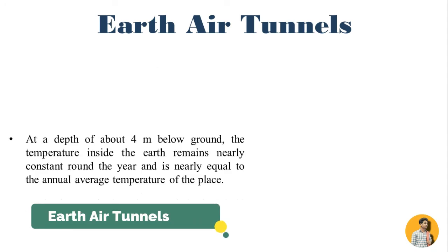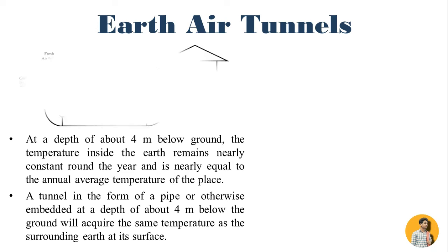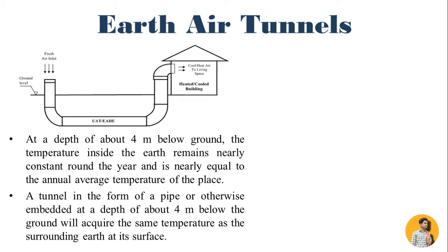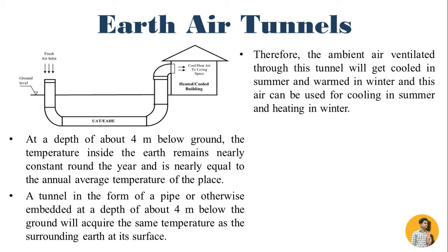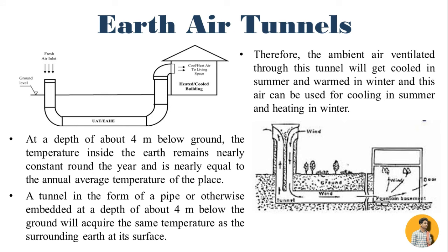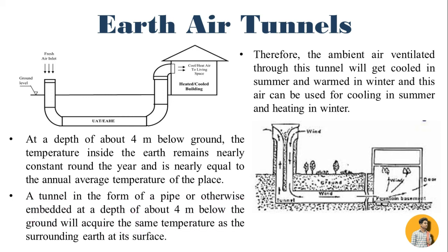Earth air tunnels: at a depth of about 4 meters below ground, the temperature inside the earth remains nearly constant around the year and is nearly equal to the annual average temperature of the place. A tunnel embedded at a depth of about 4 meters below ground will acquire the same temperature as the surrounding earth. Therefore, ambient air ventilated through this tunnel will get cooled in summer and warmed in winter, and can be used for cooling in summer and heating in winter.